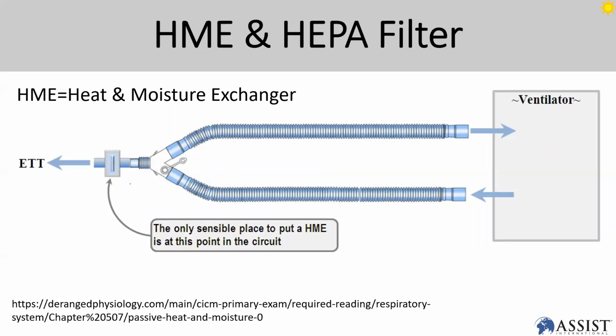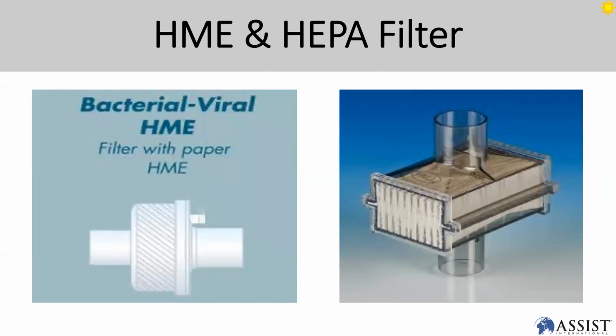So when you talk about the circuit, the HME and HEPA filter play a very important role in the circuit of the ventilator. Basically, HME is heat and moisture exchange, and the HEPA filter is used on the exhalation point to breathe out, to make sure there is no cross infection on the ventilator. This is the type of HME and HEPA filter that you're going to see normally. It plays a very important role during COVID, and even in normal conditions, because you don't want any cross infection when using a ventilator. When you exchange patients, you don't want any cross infection between the patients.